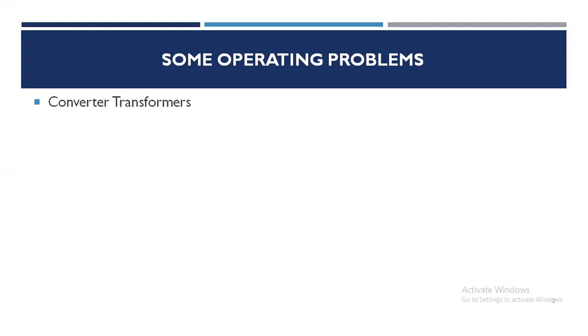The effect of repetitive commutation transients has been identified as potentially harmful, particularly during high firing angle operations. This is aggravated by the effect of copper sulfide deposition on the electric field distribution. It has been shown that the commutation failures in the upper rectifier bridge may result in voltage stresses in the lower bridge in excess of the stresses caused during the DC insulation test.